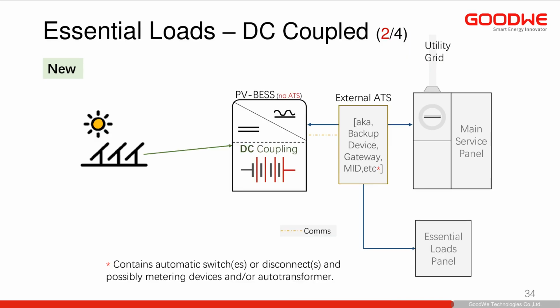In a different design, we can have no ATS, right, as part of our ESS. It's not embedded, so you have to have something external. It's got a lot of different names. MID is really not the appropriate name for this location of the device, but you will see a lot of different names for these. So you'll have to make sure you get that external device.